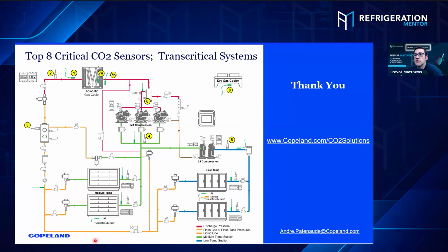Okay, for the first question: is the switch done when you have an OL, so out of limit, a short or extreme high ohms? Is that for the redundant sensor? So if you get an OL, you get a shorted sensor, or it goes out of range, that's when it will trigger the redundant sensor. So I think that's what the question was.